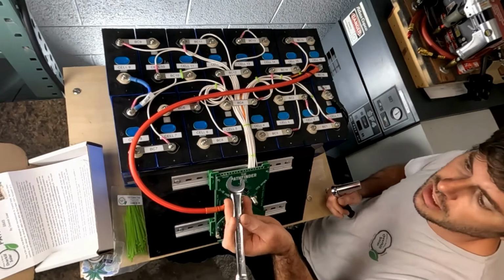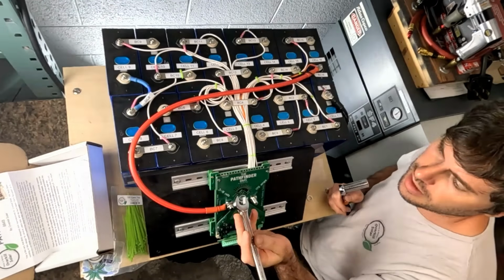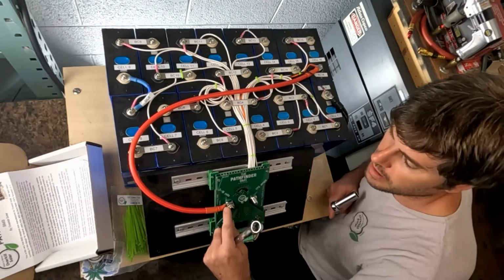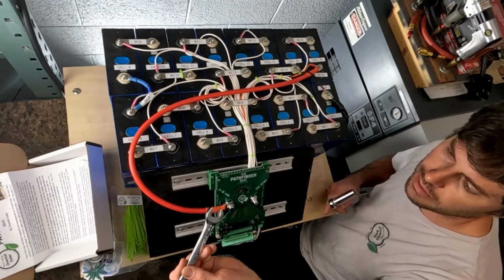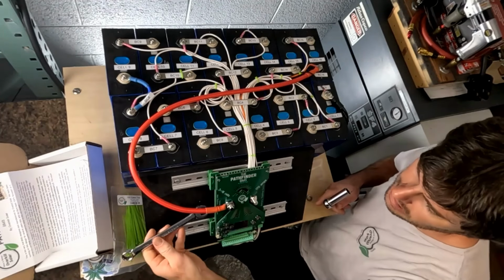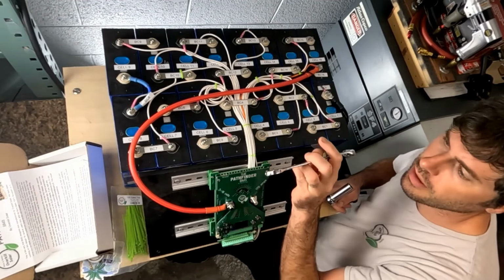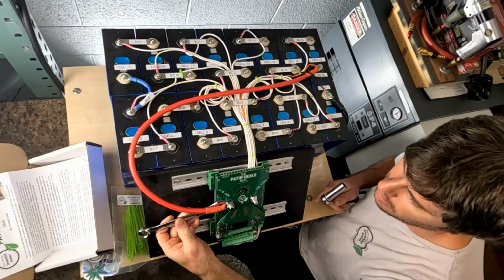It's important if you're using a wrench to tighten this that the wrench is thinner than the space under the terminal, or else when you tighten it, it'll pinch the circuit board and damage it. So make sure your wrench is thinner than 8 millimeters.